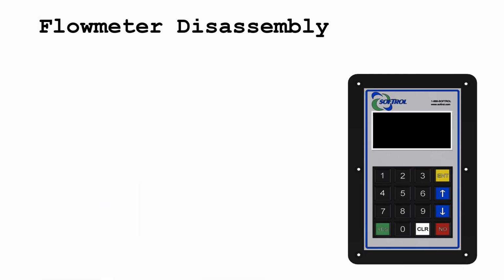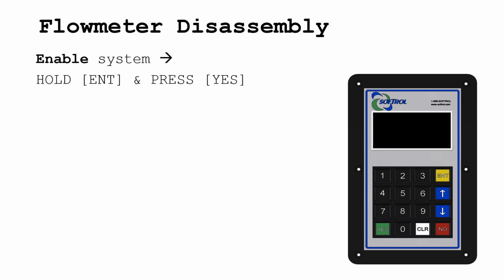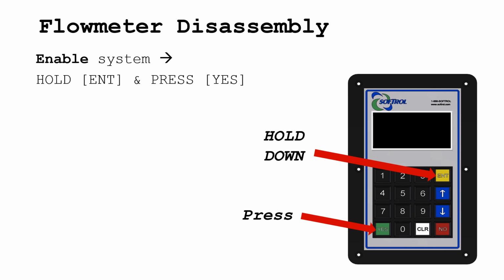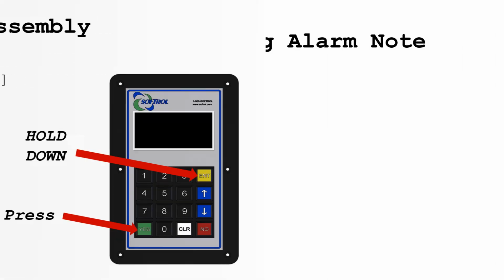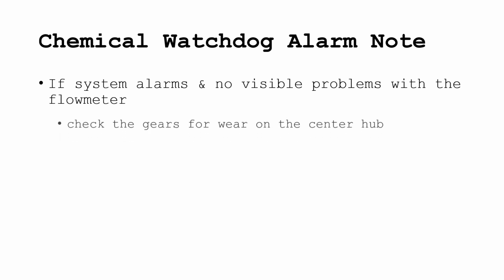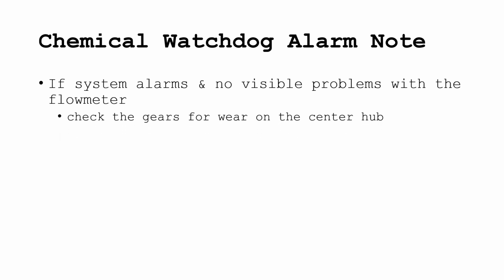After you are done reinstalling the flow meter, don't forget to enable the system, by holding down the ENT key and then pressing the yes key, to resume normal operations. Note, if the system alarms with no visible problems to the flow meter, check the gears for wear on the center hub. Gears should rotate freely on the pins, but should not wobble.